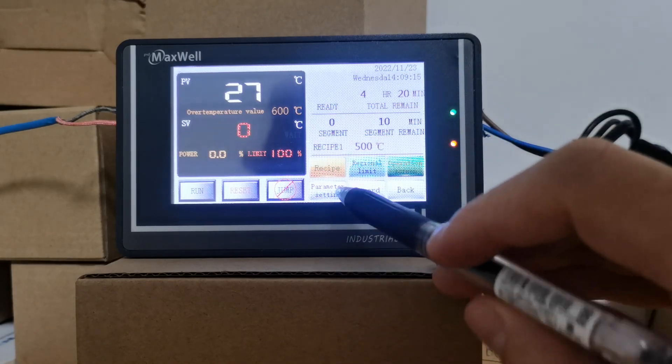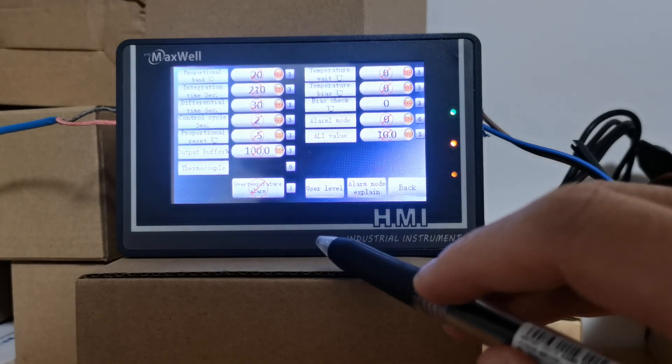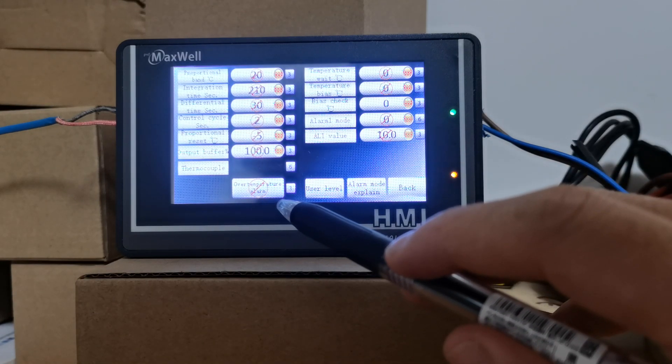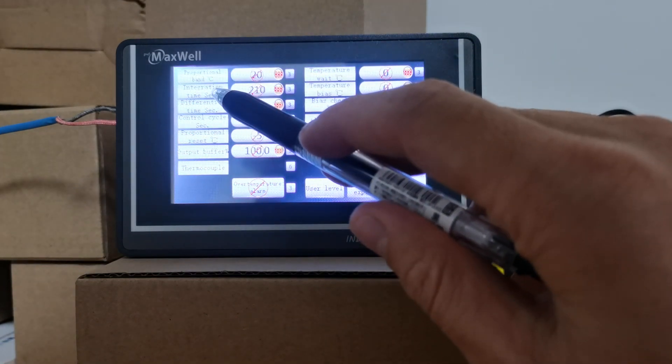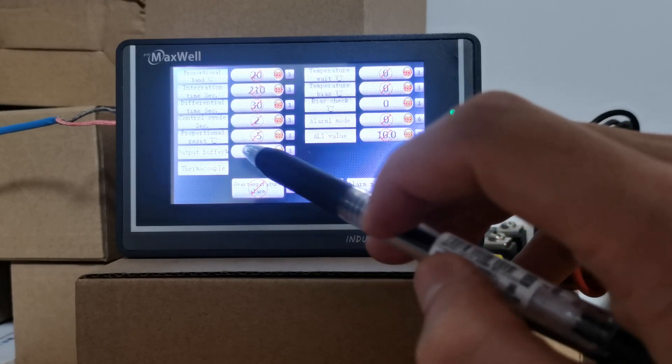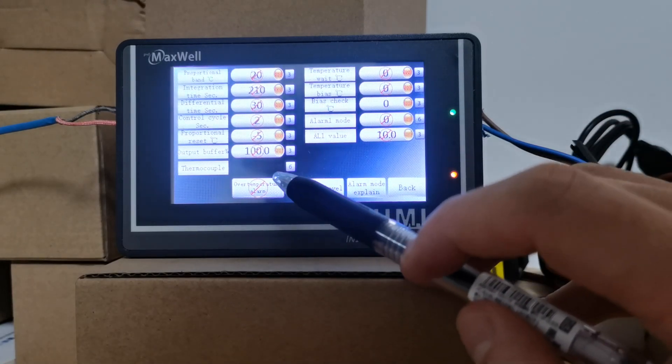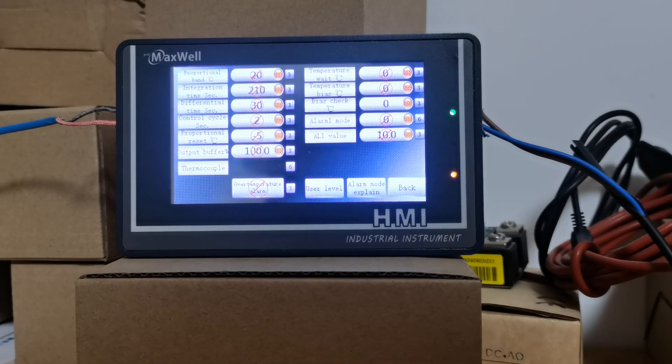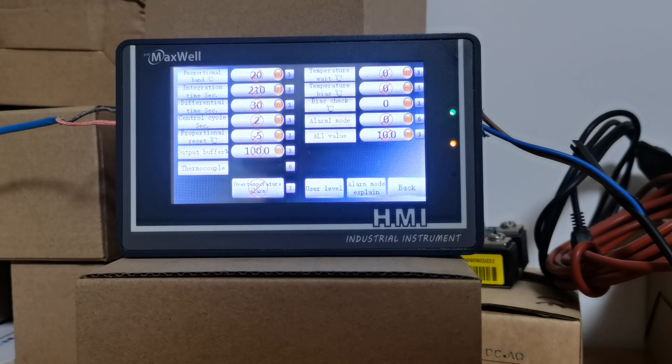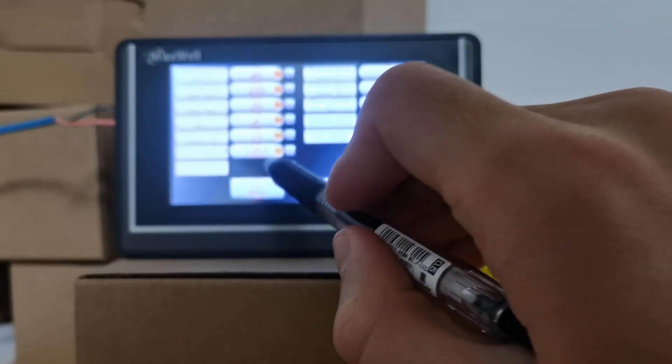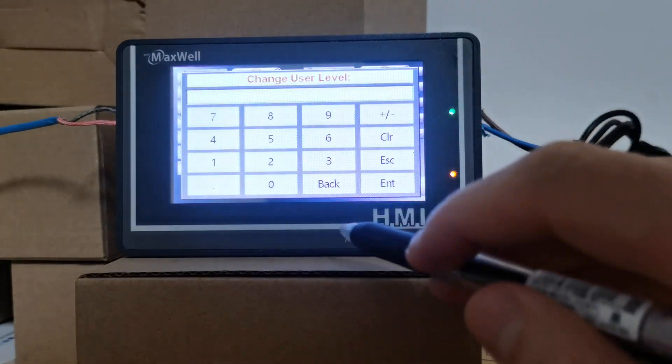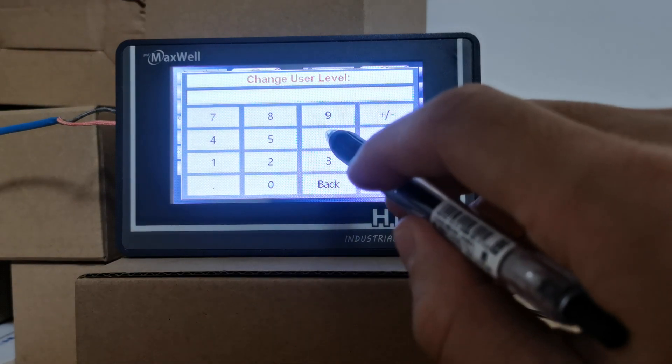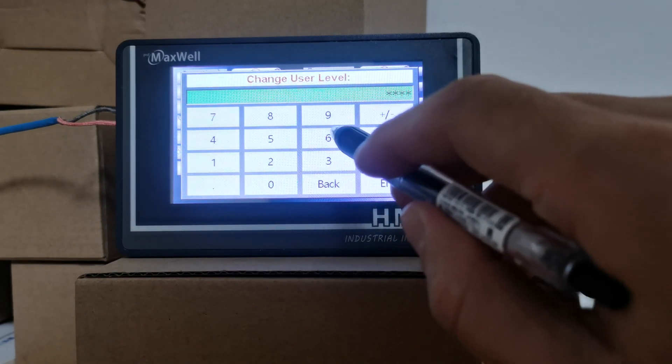Here you have the parameter setting where you can set the proportional band, integration time, differential time, control cycle. You can change the input settings - for example, the default input setting is type K thermocouple. You can change to type J. Click the password and the password is six six six six six six.